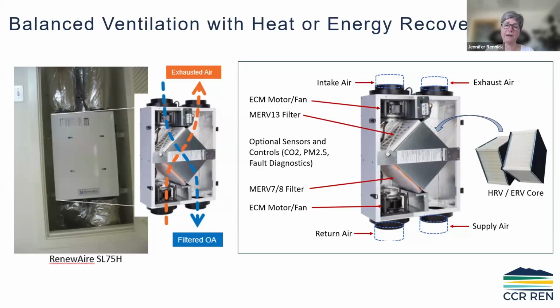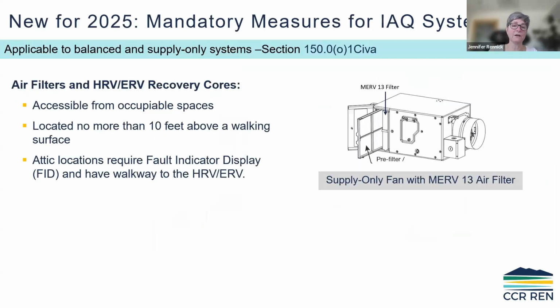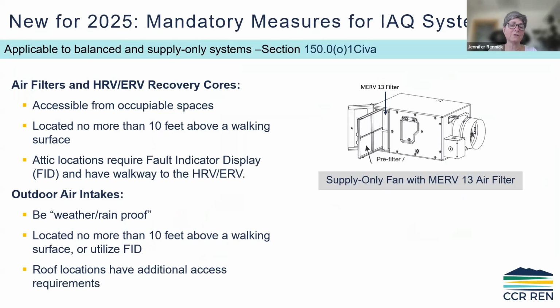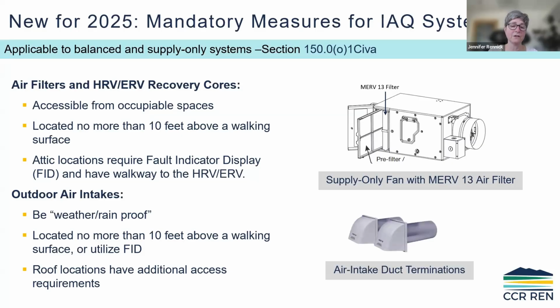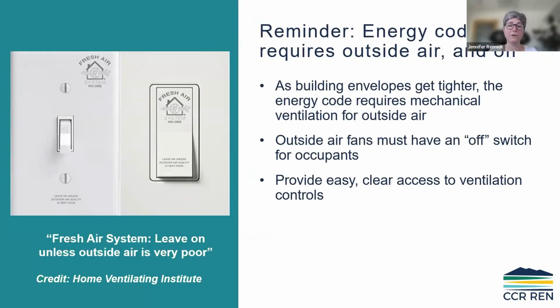But there are filters and HRV or ERV cores that need to be accessed, and these things have to be maintained. So as a result, there are specific requirements that these appliances be accessible no more than 10 feet above a walking surface, and attic locations require special controls that say, hey, something's wrong, a so-called fault indicator display. And then there are also some requirements for the outdoor air intakes themselves, that they be protected from weather. And then, as a reminder, part of the code is that we have the ability to turn these systems off in case of poor outdoor air quality, such as wildfire.